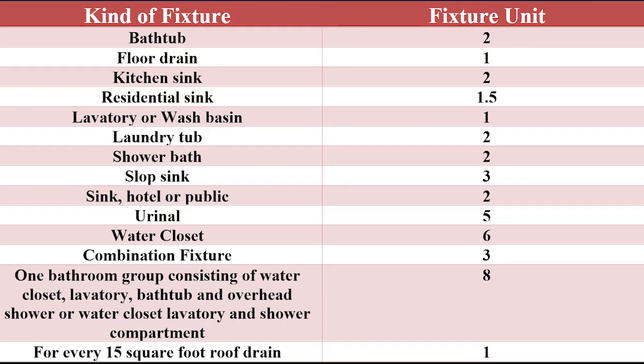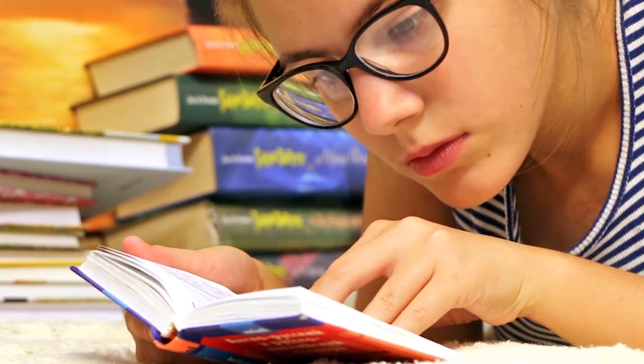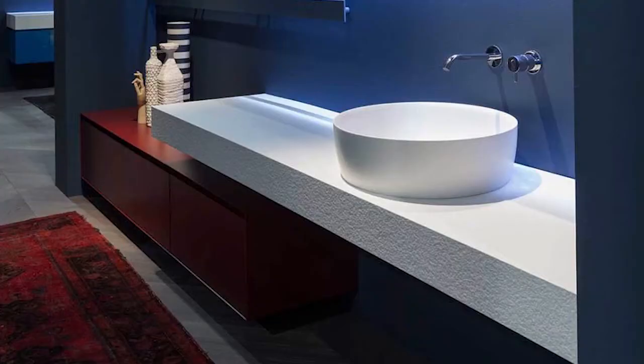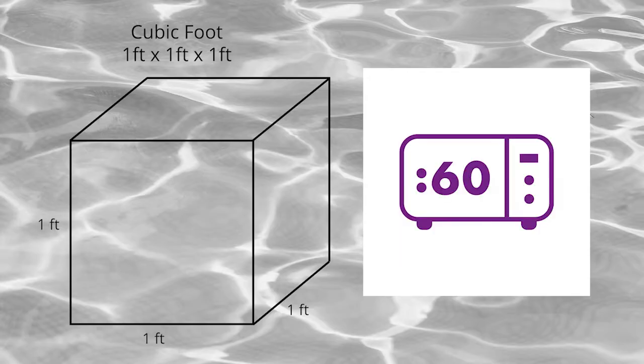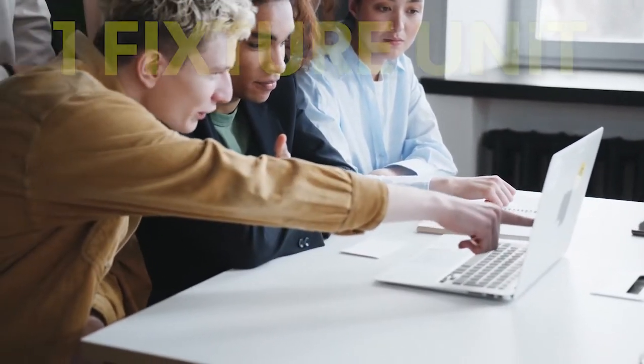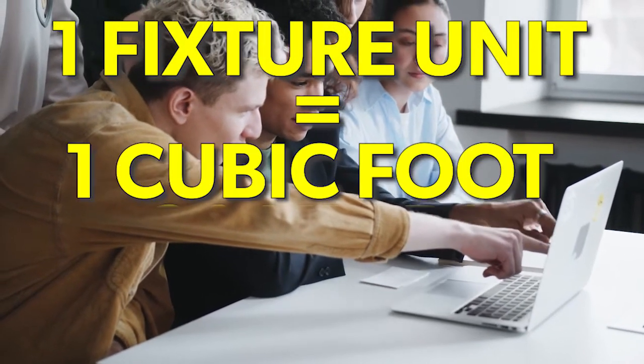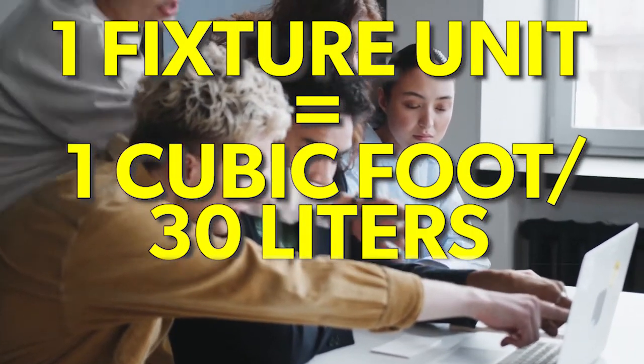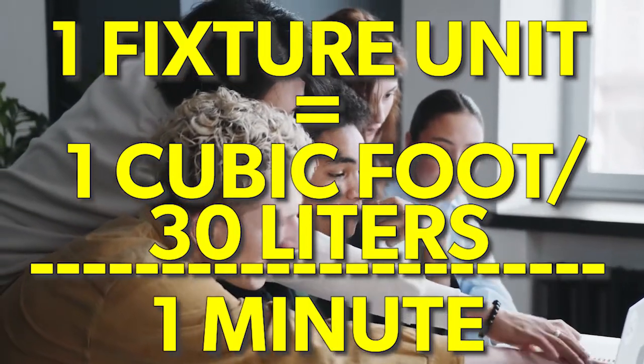And an 8 fixture unit for 1 bathroom consisting of water closet, lavatory, bathtub, and overhead shower, or water closet, lavatory, and shower compartment. Based on their findings, the wash basin, being one of the smallest fixtures, discharged waste at approximately 1 cubic foot of water per minute interval. The committee finally decided to establish the unit fixture and called the water discharge as one fixture unit, representing 1 cubic foot or 30 liters of waste discharged by the fixture in a 1 minute interval.